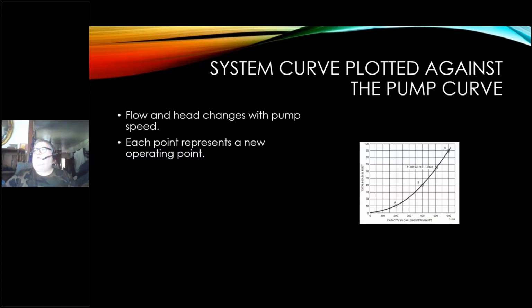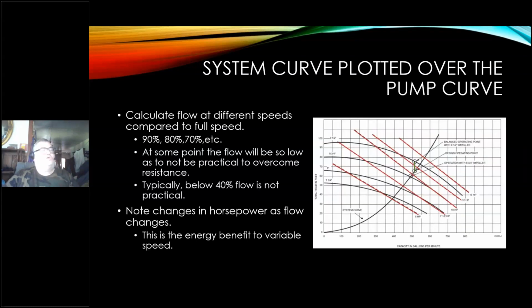It's plotted against a pump curve. I'll use the old one I gave you as an example, but this is a system curve with different points on the system operation, and each one of these, A, B, C, flow at full load, and so on, represents where we're going to operate against the pump curve. Each one of them is a new point, but it's calculated out of those calculations. So if I plot my system curve over the pump curves, we calculate the flow at different speeds. This is where our variable speed comes in. We start looking at what the system looks like and what the pump operation looks like against that system curve.